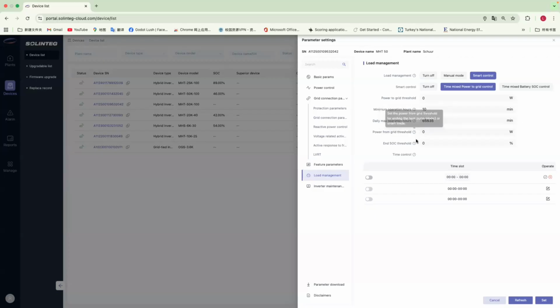We can also set values to stop the smart devices from running. For example, we can set the power from grid threshold, meaning that if the power taken from the grid to run this system is higher than the value set here, the smart device will enter the turn-off status. We can also set the end SOC threshold, meaning that if we take more power from the battery and the battery's SOC reaches this end SOC threshold, the smart devices won't be able to work.